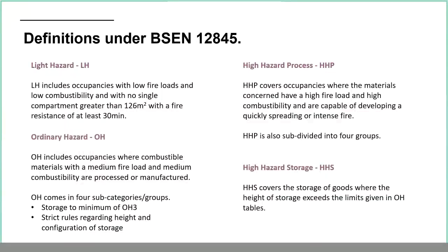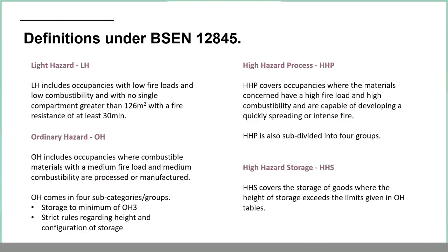Under BSEN 12845, there are definitions for light hazard, ordinary hazard, and high hazard. High hazard is split into two types: high hazard process and high hazard storage. High hazard process is about what you're doing — welding, hot works, machines running hot — whereas high hazard storage is about storing goods closely together in racks or bays. In some cases you have a bit of both.